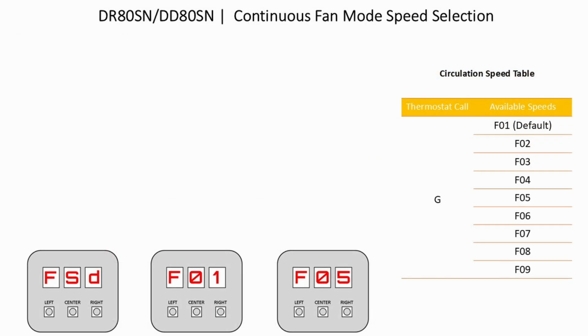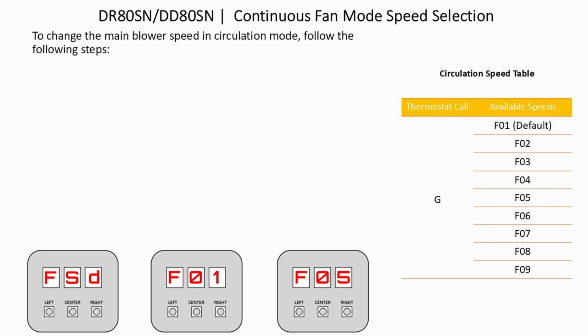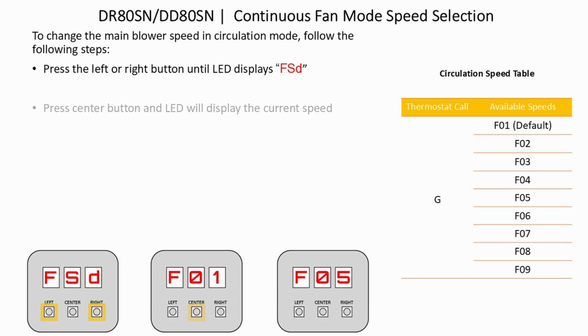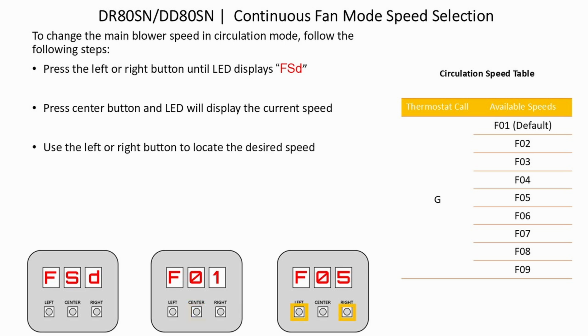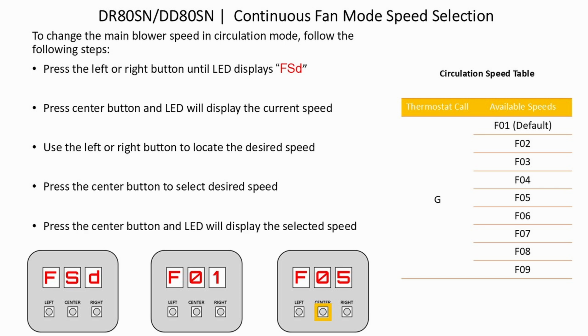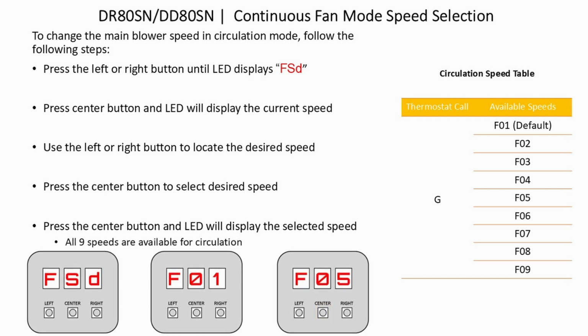DR80SN, DD80SN, continuous fan mode speed selection. To change the main blower speed in circulation mode, follow these steps. Press the left or right button until the LED displays FSD. Press the center button and the LED will display the current speed. Use the left or right button to locate the desired speed. Press the center button to select the desired speed. Press the center button and the LED will display the selected speed. All 9 speeds are available for circulation mode.